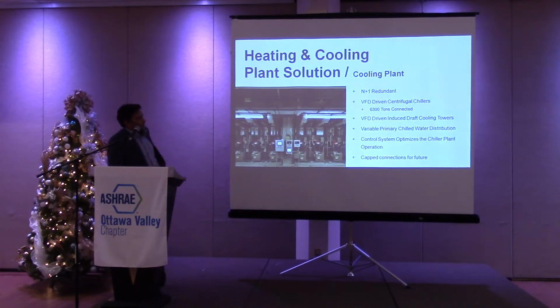We had magnetic bearing chillers that were variable speed drive, as well as the heat recovery chillers that I noted before. Again, primary variable chilled water distribution to maximize efficiency, including VFDs on the cooling towers. We spent a lot of time optimizing this chiller plant, and it's not done yet. Right?